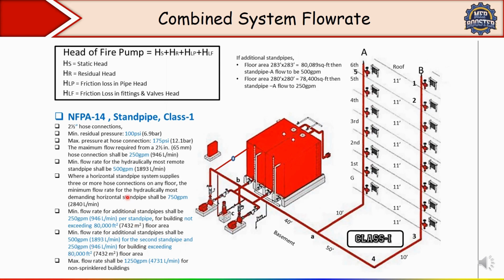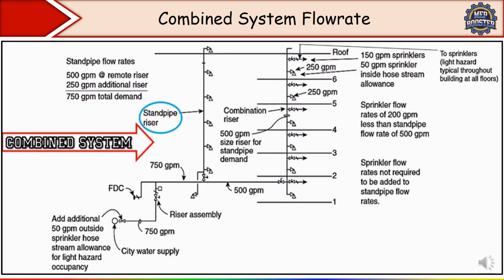Correct? Remember. So let's say in the example which I have shown, suppose our building area is less than 80,000 square feet floor area. Correct? So the minimum flow rate for the additional standpipe is 250, and for the most remote standpipe 500. The same is written here. As we have seen, this is a 2.5 inch hose connection. So for the most remote standpipe, how much? 500 GPM, correct? And if it is an additional one, 250. So here I have added 500 GPM for the most remote riser and 250 for the additional riser.